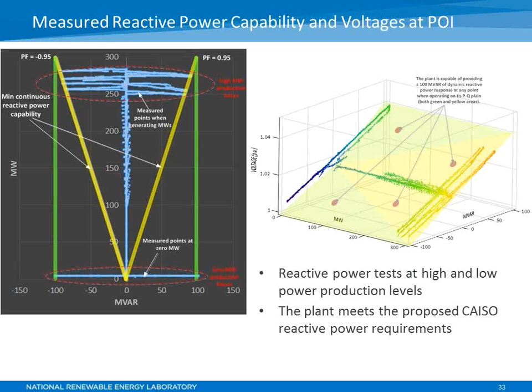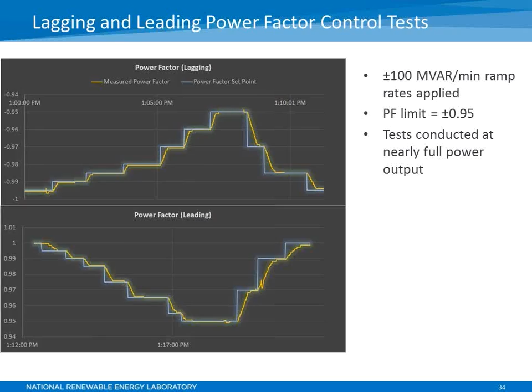So let's move on. This is a result of plant operation in a power factor control mode. The plant was following the power factor set point signal and the power factor measured at the point of interconnection. And again, you see that the plant provides very good and accurate power factor control in this plus minus 0.95 power factor range in both cases.